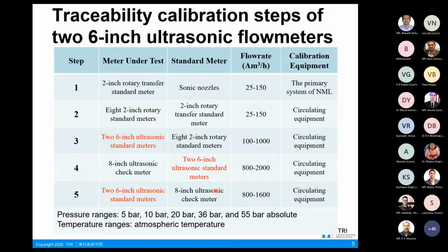The data regression in this paper is extracted from the calibration results of one of the two 6-inch ultrasonic flow meters, and the calibration data of the third and fifth steps in this table are used. The data at 800 and 1000 cubic meters per hour are the results of the overlapping of these two steps.